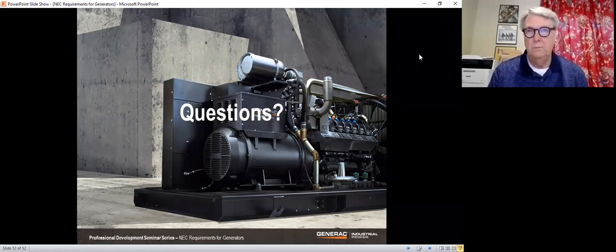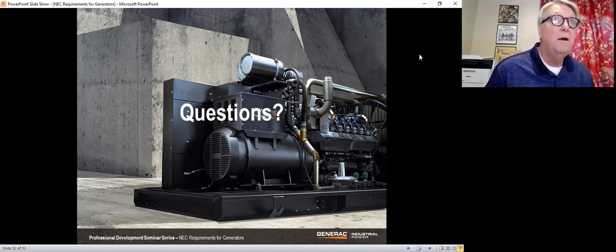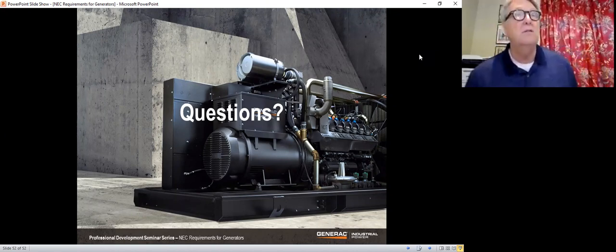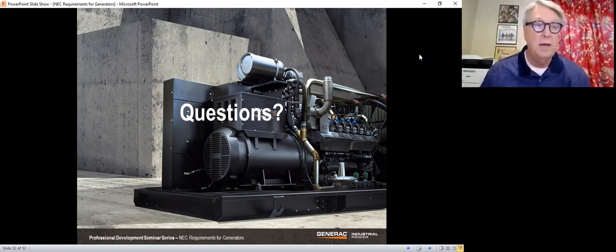What are the different people or job titles that could be an AHJ? Brett, that's a great question. Many times the AHJ is typically going to be the guy that comes on site and looks at that generator and signs off on it. So typically I would say the AHJ is going to be your electrical inspector, but because it's got an engine in there and because there are fire limitations and so on, and fuel could make a difference to that, the AHJ could very well be the fire marshal.